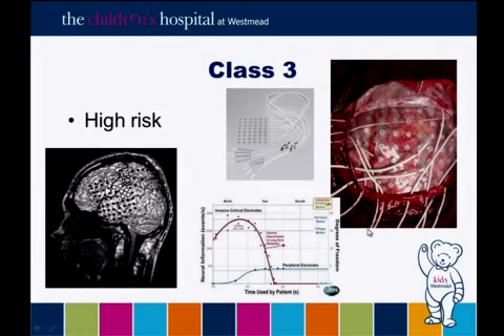Cochlear implants, the bionic ear, are eons ahead of their time. They've tried to use the same technology to replace artificial eyes, with electrode arrays separated by silicon, but they can't manufacture that fine enough to go in the retina. It's just not going to work, right? So there are other types of electrode arrays that will go into the retina, and they've got functional ones that are now up to 1,000 electrodes that will implant into your retina, so you get a visual field with a resolution of about 1 in 1,000. You'll probably hear about those shortly.